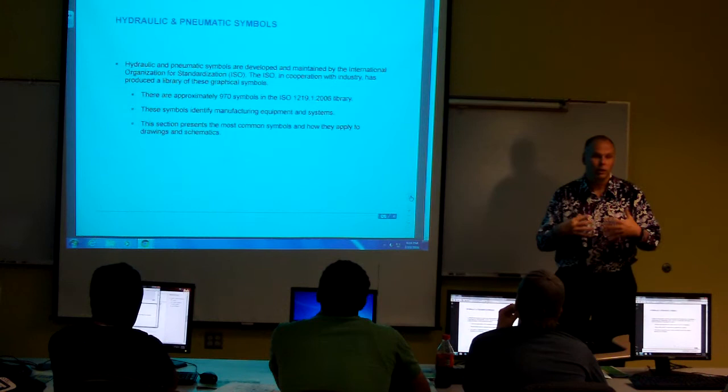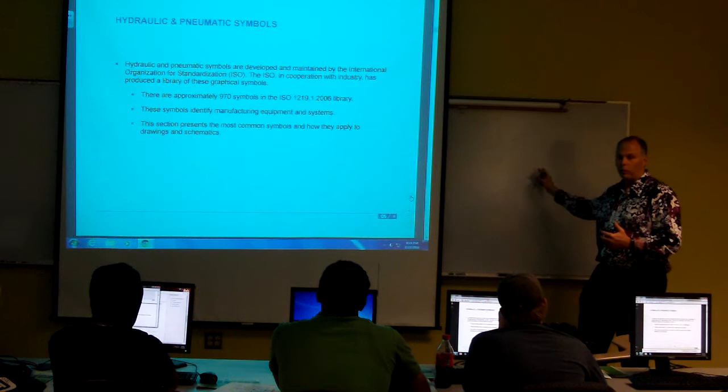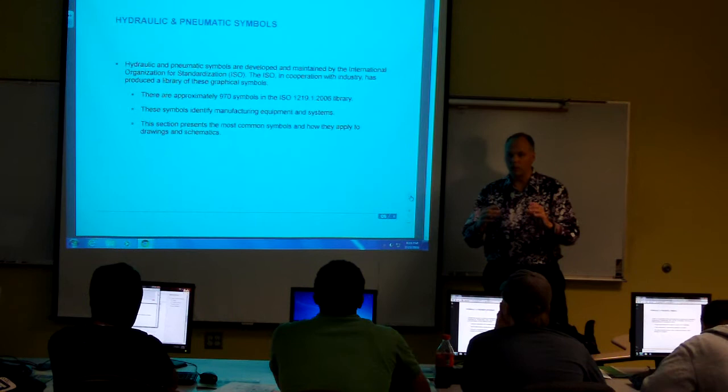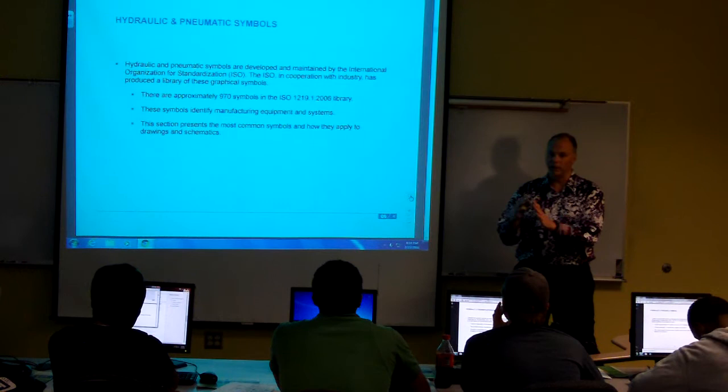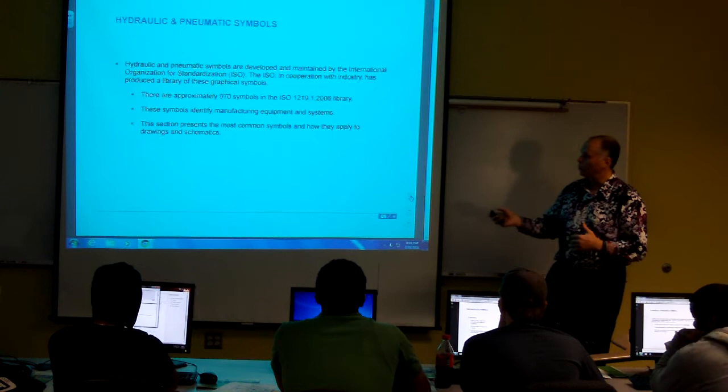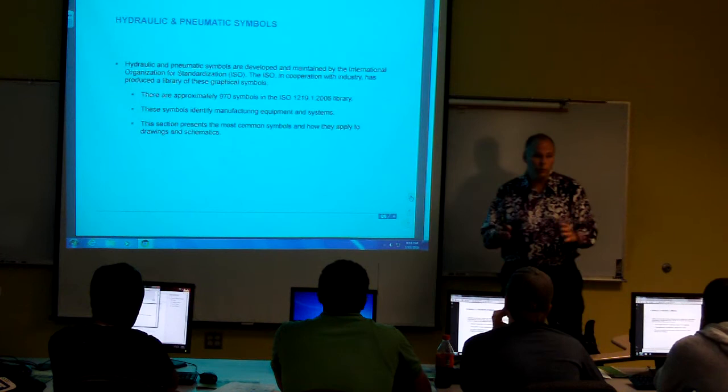What we're going to do is teach you building blocks of what to look for. Remember the other day I drew up here three blocks? Well, when you see three blocks, you're going to start to build your mind of what those are, what that is. It's going to really help you identify. You're not going to memorize all 970. I wouldn't expect you to. But if you start seeing certain pieces of it, well, this thing has like a little springy on it. Well, that must tell me it has a spring return of some sort. This thing has an open arrow. Well, it must be air. It must be pneumatic instead of a closed arrow for hydraulic. So those are things that we're going to teach you.